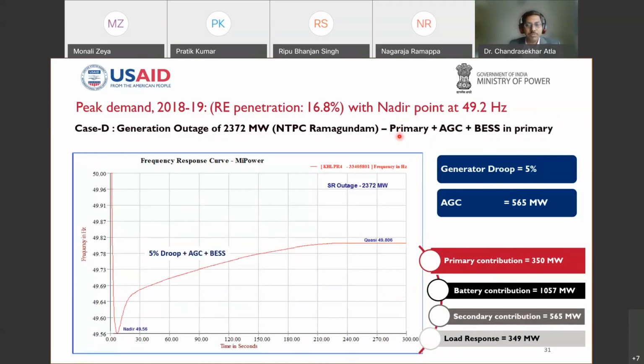If I enable primary and secondary contribution from the conventional generation and BES in the primary, you can see here, because BES is operating in the primary, my frequency is improved and it is 49.56. Then from around 30 seconds, secondary reserves also start participating, and primary reserves continue up to 30-50 seconds. After that, primary reserves continue, and in addition AGC secondary reserves will be there, and you get a quasi steady state of 49.8.